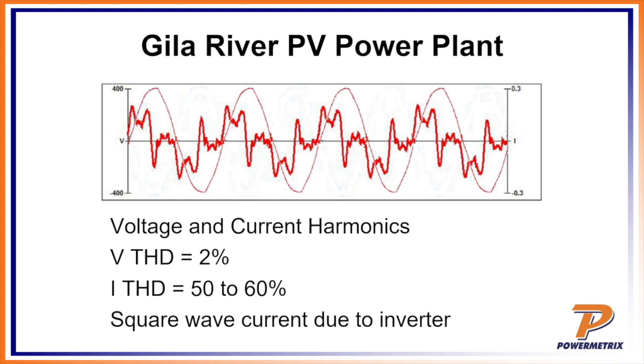Harmonics are pretty terrible, but that's not that uncommon to see based on the inverter. Notice that the currents look kind of like a square here, and that usually shows a switching power supply or an inverter, which is pretty common in the technology on those solar power plants.